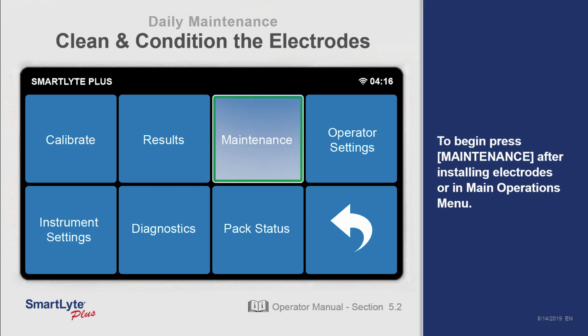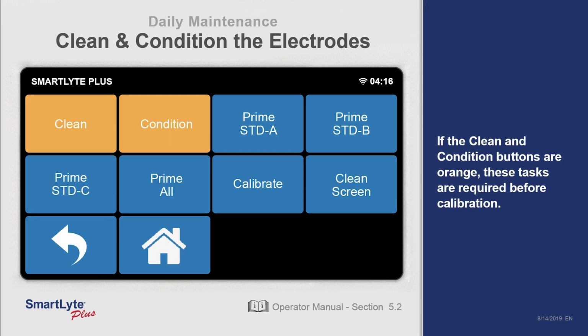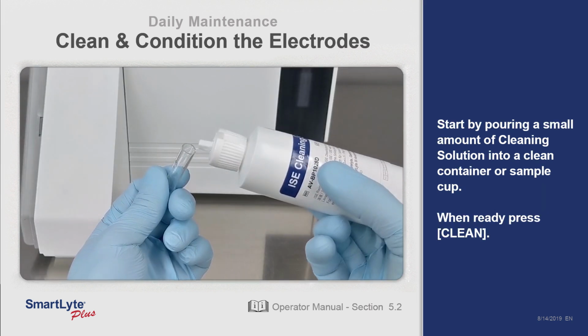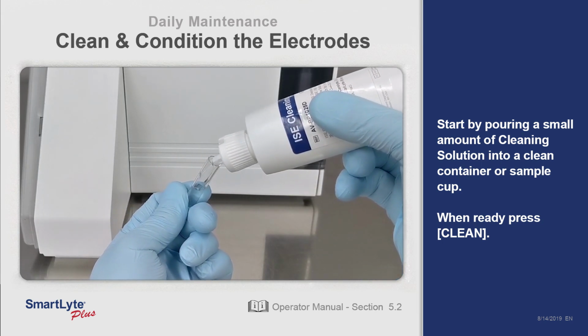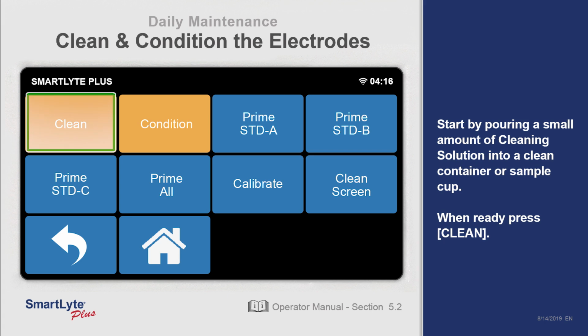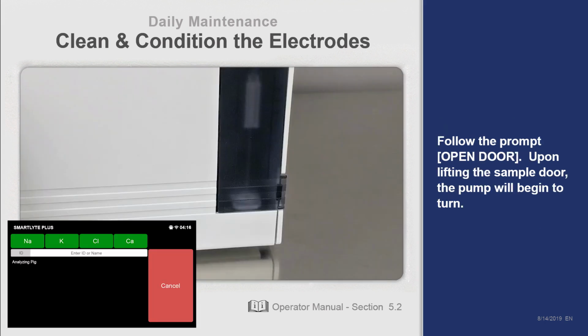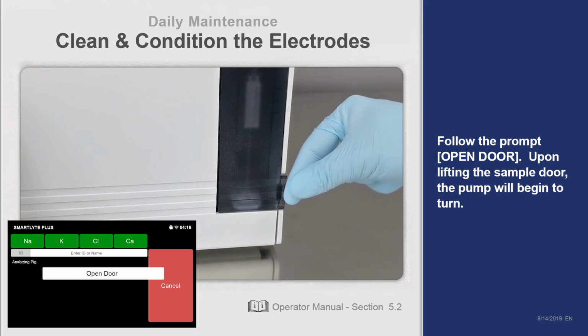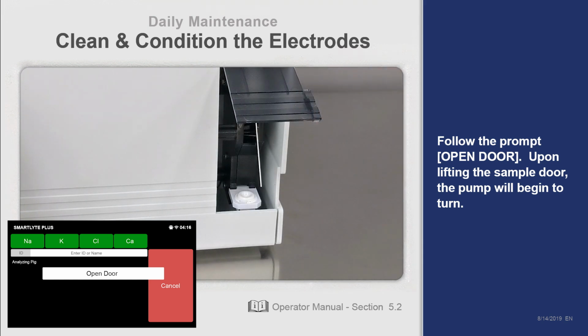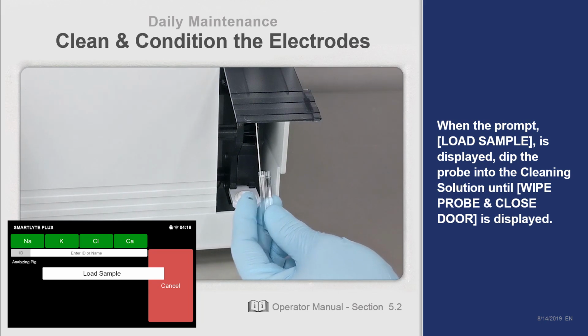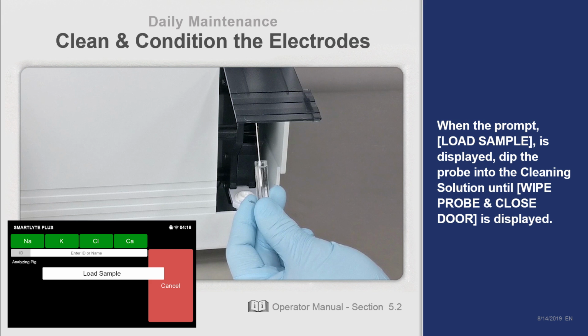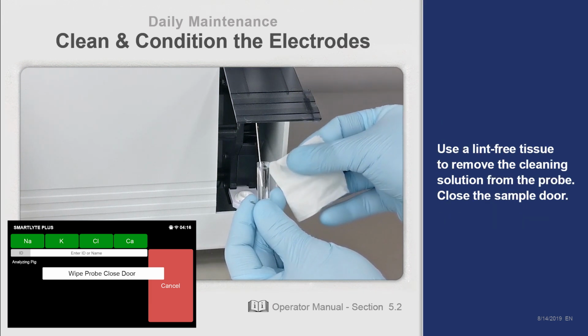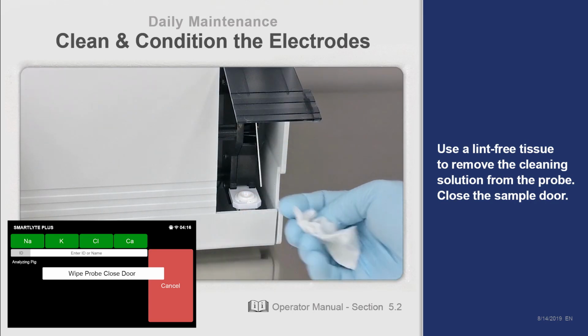To begin, press Maintenance after installing electrodes or in the main operations menu. If the Clean and Condition buttons are orange, these tasks are required before calibration. Start by pouring a small amount of cleaning solution into a cleaning container or sample cup. On the display, press Clean. Follow the prompt Open Door. Upon lifting the sample door, the pump will begin to turn. When the prompt Load Sample is displayed, dip the probe into the cleaning solution until the Wipe Probe & Close Door prompt is displayed. Use a lint-free tissue to remove the cleaning solution from the probe and then close the sample door.